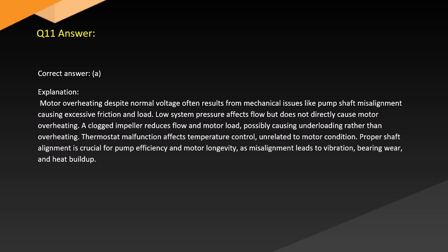Answer. Correct answer: A. Explanation. Motor overheating despite normal voltage often results from mechanical issues like pump shaft misalignment causing excessive friction and load. Low system pressure affects flow but does not directly cause motor overheating. A clogged impeller reduces flow and motor load, possibly causing underloading rather than overheating. Thermostat malfunction affects temperature control, unrelated to motor condition. Proper shaft alignment is crucial for pump efficiency and motor longevity, as misalignment leads to vibration, bearing wear, and heat buildup.